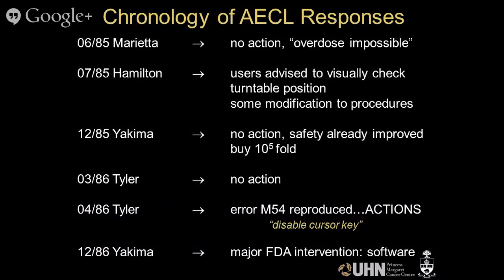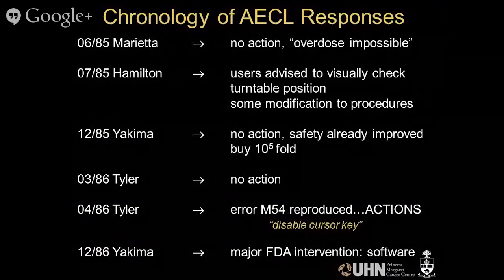So just to remember, June of '85, no action, overdose impossible. In Hamilton, we were advised to visually check the turntable position, with some modification to procedures. Yakima, no action; we were told the safety was 100,000 times better. Tyler, no action. Tyler, it was reproduced. The action was to disable the key. So we were all instructed to physically remove the plastic key over that particular cursor control so that we couldn't enter the prescription so quickly. And then finally, after the second Yakima incident, FDA intervened in a major way.